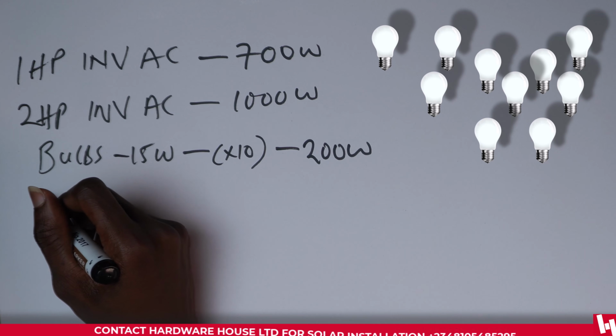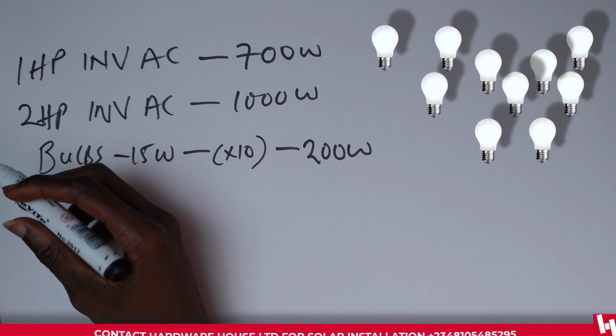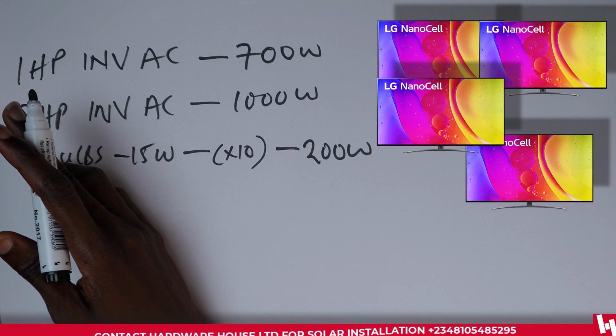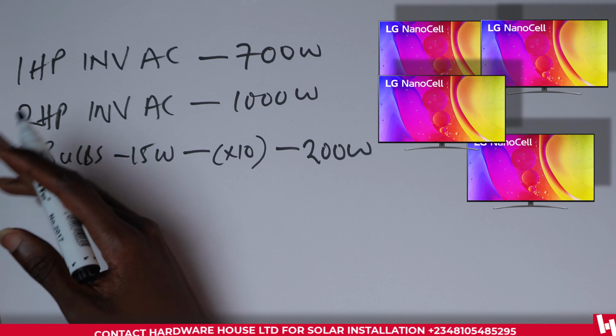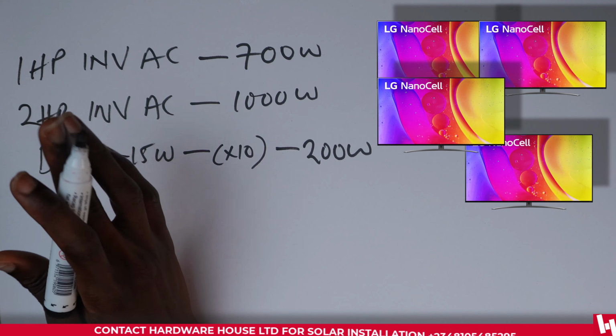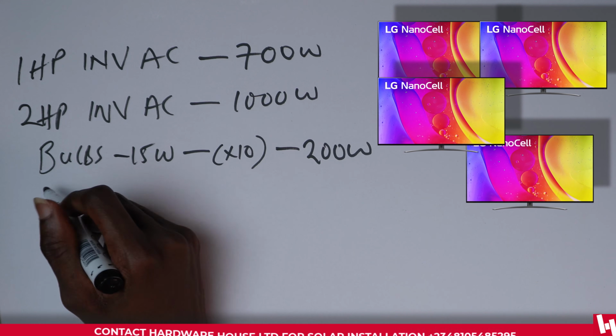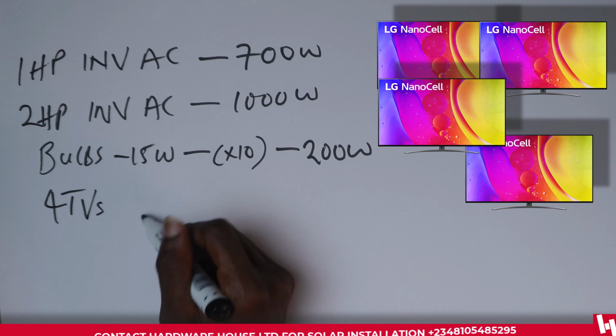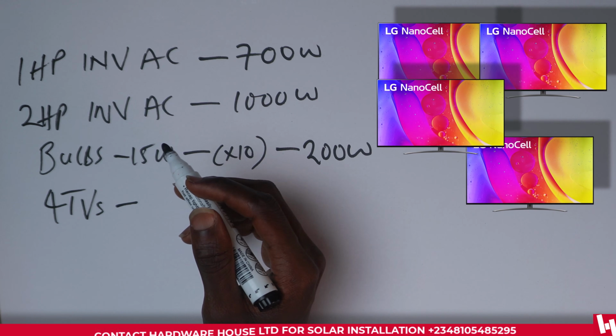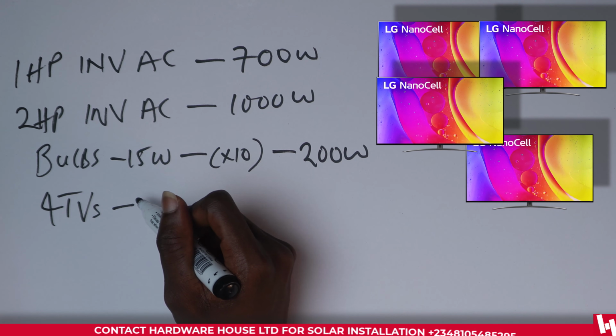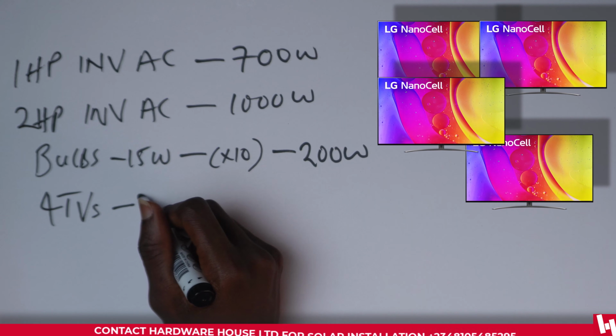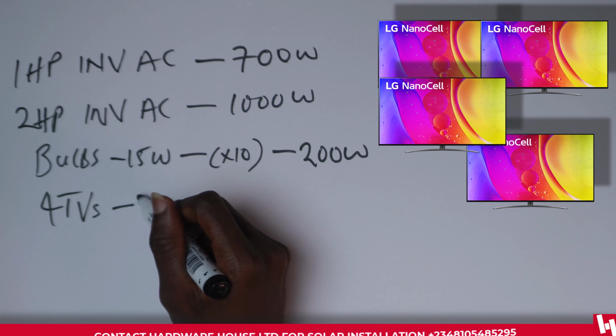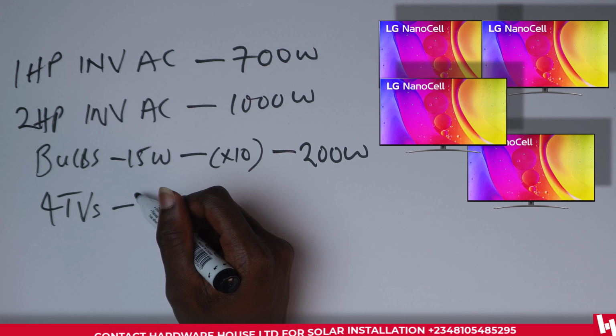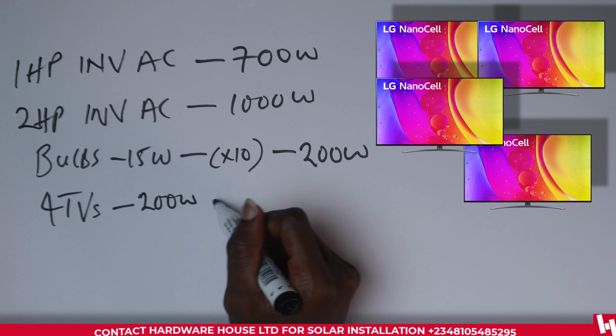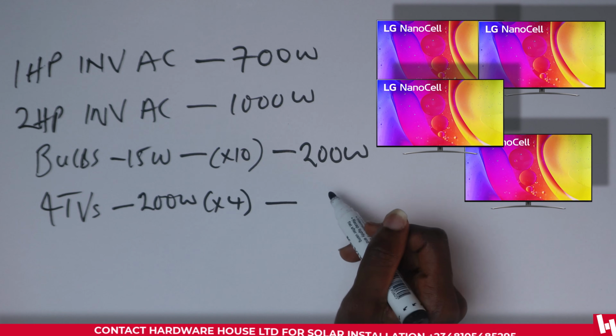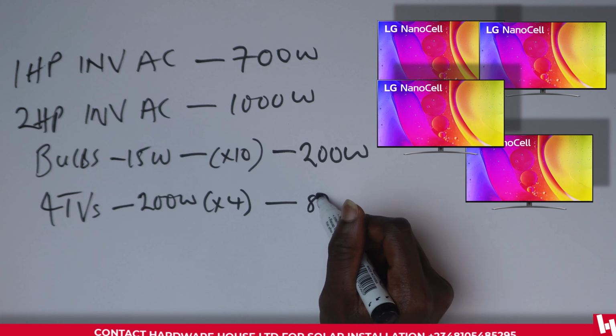The house also has about 5 bedrooms, so let's do 4 TVs. So even if you have a 4 bedroom, or a 3 to 2 bedroom, you can use 2 TVs or 3 TVs, or let's max it out at 4 TVs. So we have an extra allowance if all TVs are not functioning at the same time. So we will be allocating 200 watts because that is what most big smart TVs consume at maximum usage. But there would also be some allowance from this as well. So we would do 200 watts times 4. So we have a total of 800 watts for TVs alone.